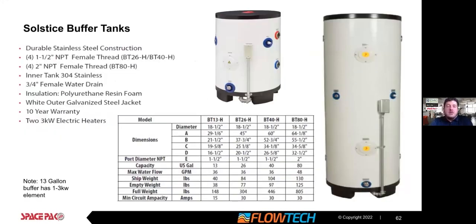Faster. Get into buffer tanks a bit. Buffer tanks, as mentioned, are critical components of the system. They allow us to decouple the flow rates from the outdoor unit and the system. My nickname for this is the best value in hydronics. These are amazing units. They're great value.